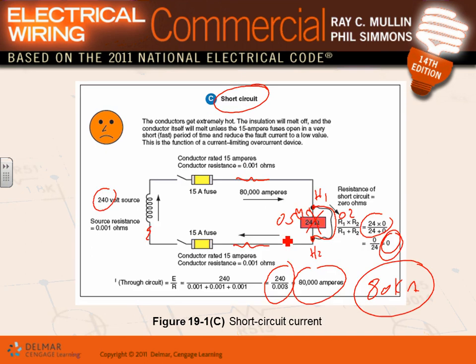The ground fault condition, guys, is not here, it's later on. The ground fault: if you take one of these phases to the ground, to the pipe, it will give you, under the worst scenario, close to 80,000 amps, but typically half of that. If you have a ground fault condition, it's typically half of the three-phase short circuit. So say a ground fault will give me a maximum of 40,000 amps in this circuit. What's a ground fault condition? You take phase A and tie it to the pipe, to the ground.